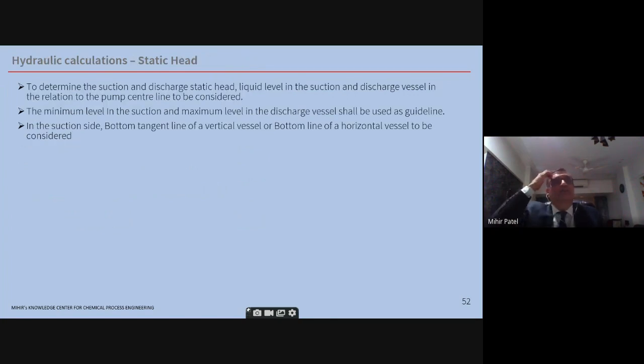Hydraulic calculations, now we come to the static head. Basically, to determine the suction and discharge static head, the liquid level in the suction and discharge vessel has to be considered. The pump suction nozzle elevation has to be considered. So these are the norms, basically. Minimum level in the suction vessel and maximum level in the discharge vessel shall be used as a guideline. On the suction side, the bottom tangent line, tan line, as it is called, of a vertical vessel, or the bottom line of a horizontal vessel, is to be considered. These are good engineering practices.